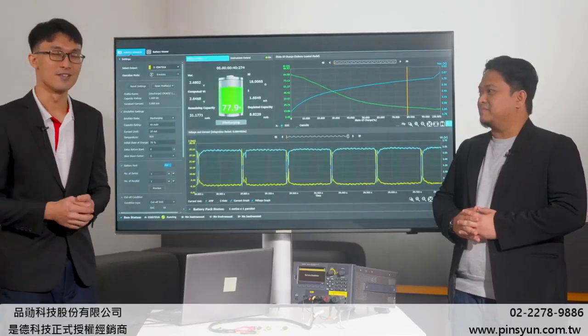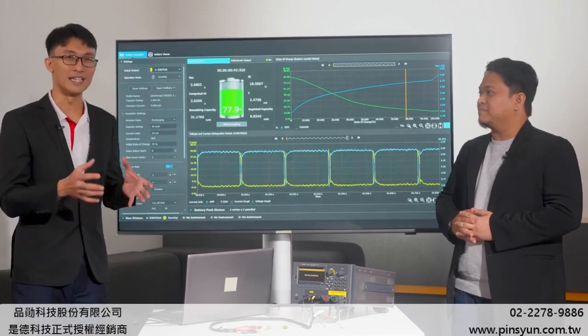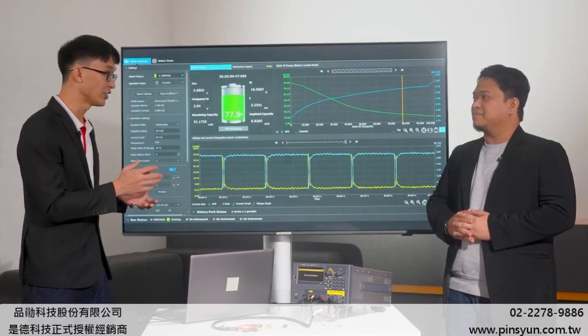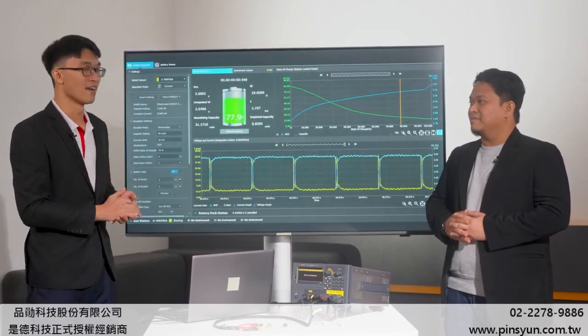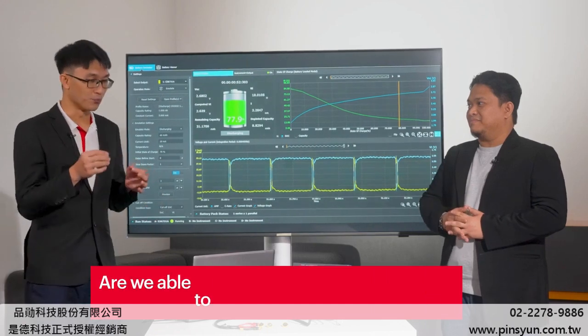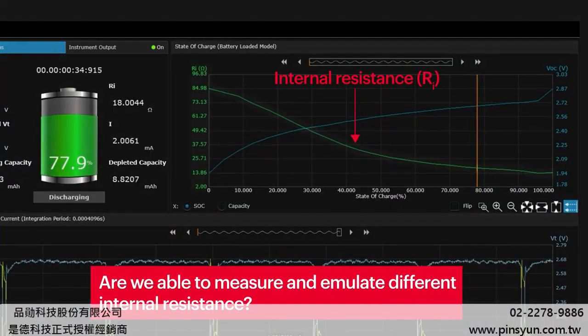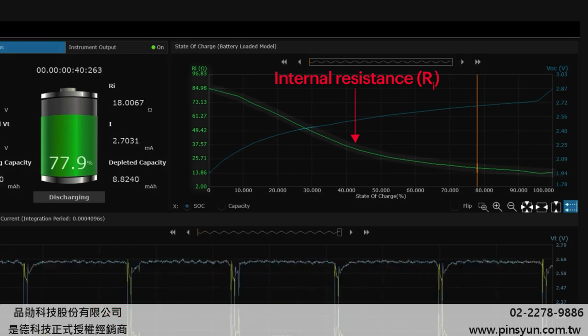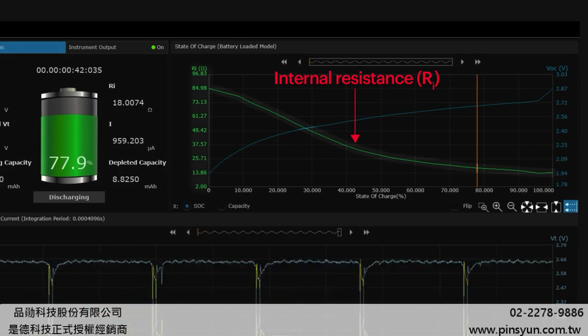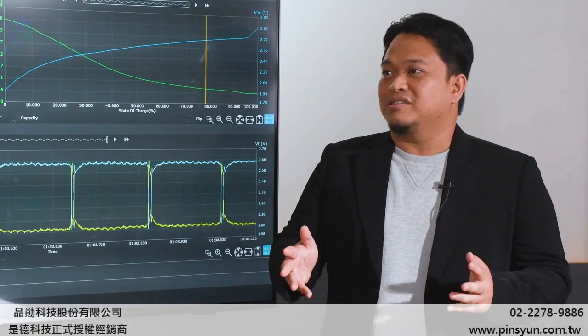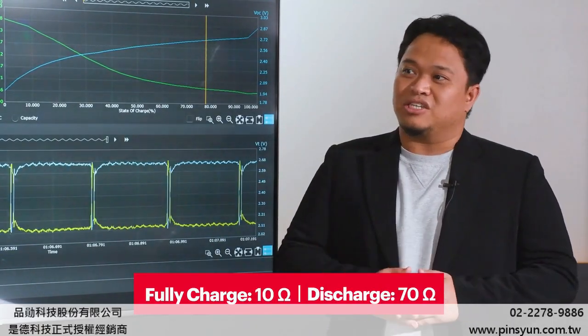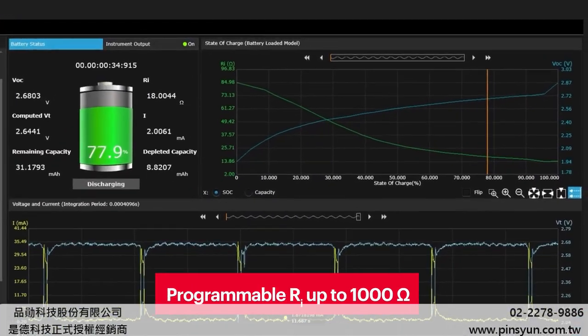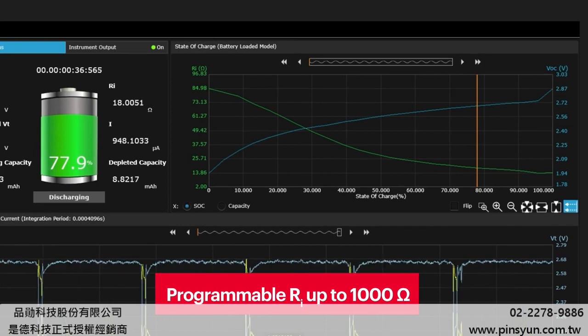That's interesting — so I can test the device without needing a physical battery? But I was wondering, as batteries age, wouldn't the internal resistance increase? Are we able to measure and emulate different internal resistances? Good question. One of the most impressive features of the instrument is its flexible internal resistance emulation. With Coincell batteries, resistance can range from 10 ohms when fully charged to over 70 ohms when discharging. The instrument is able to mimic this with a programmable internal resistance up to 1,000 ohms.